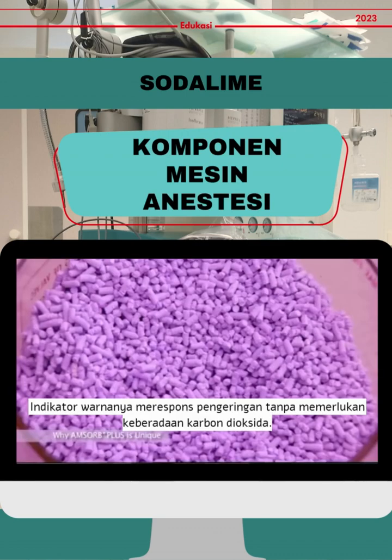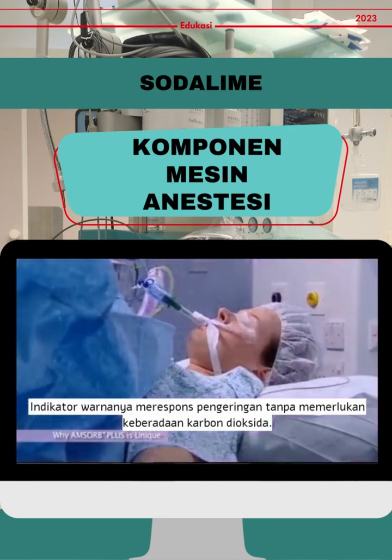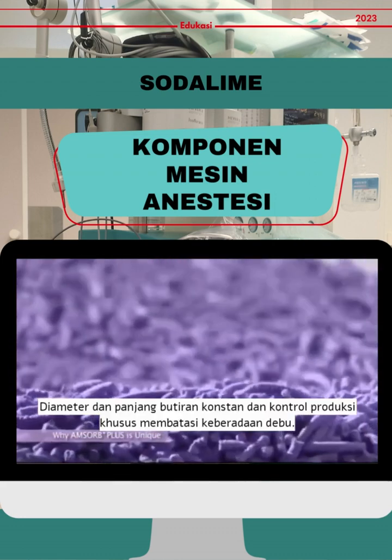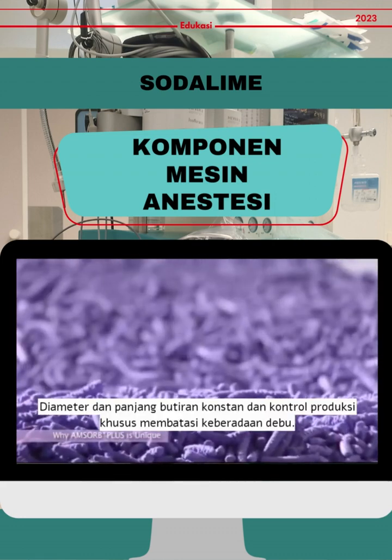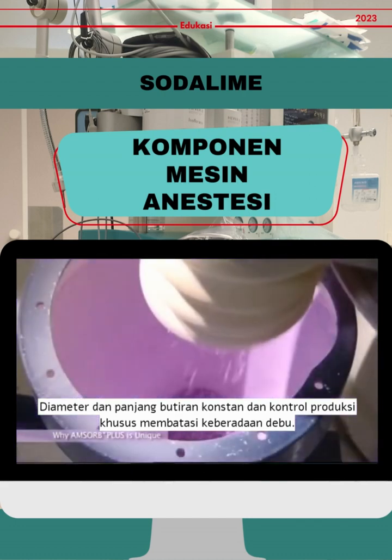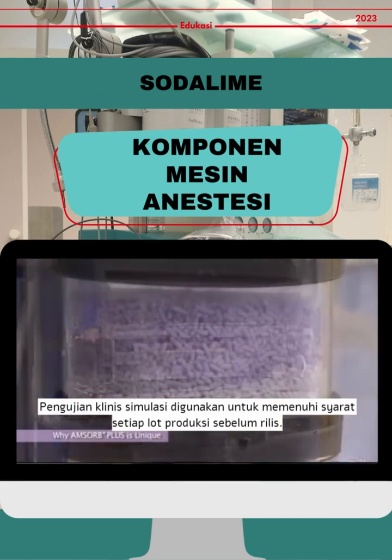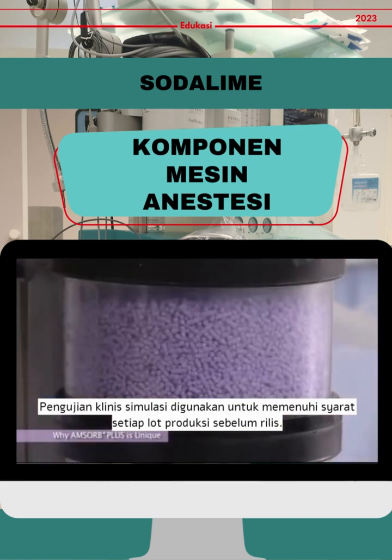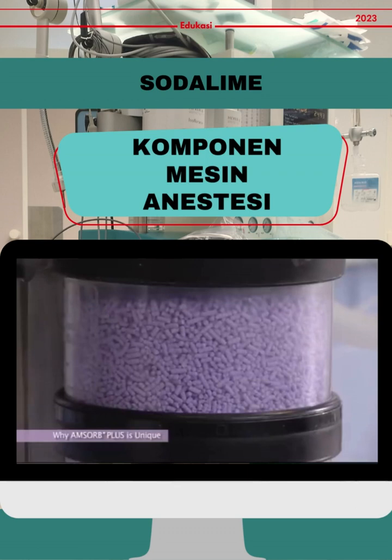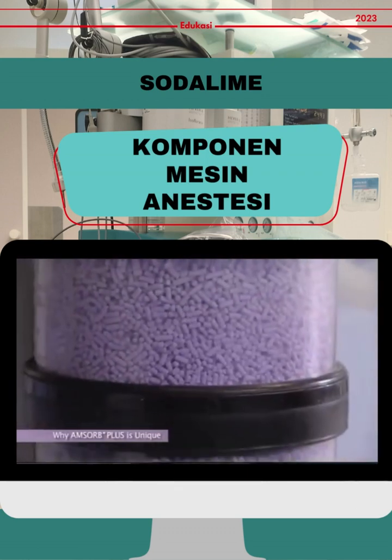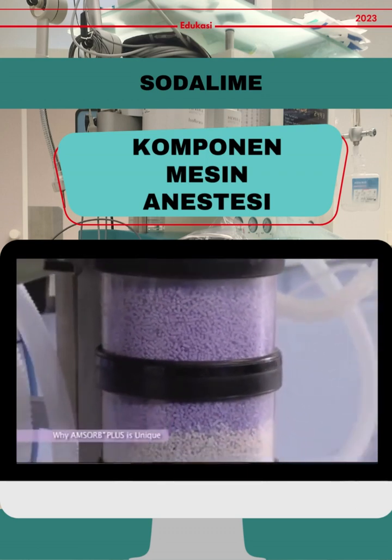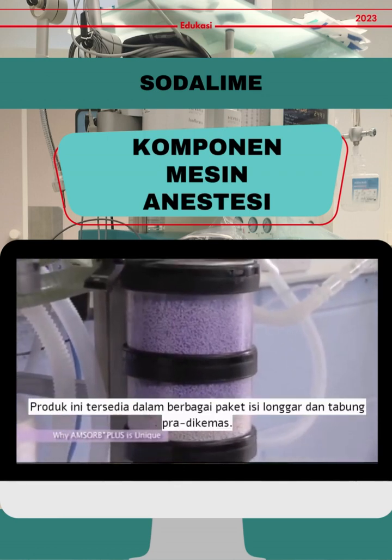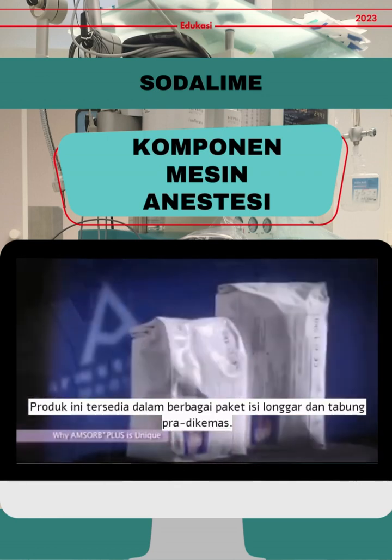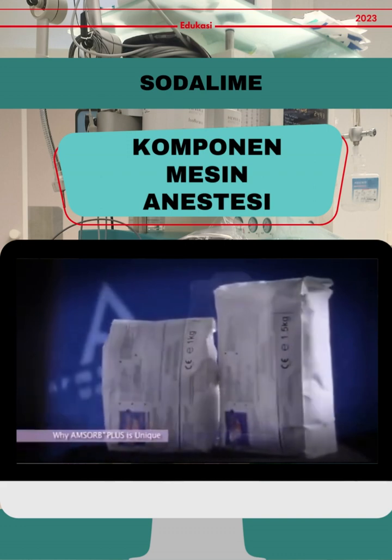Its color indicator responds to desiccation without requiring the presence of carbon dioxide. Granule diameter and length are constant, and special production controls limit the presence of dust. Simulated clinical testing is used to qualify each production lot prior to release. The product is available in a variety of loose-fill packages and pre-packed canisters.